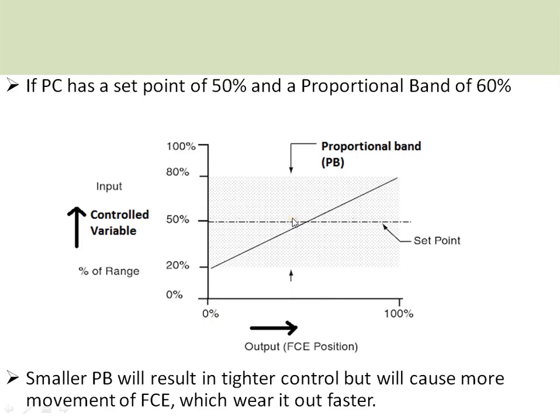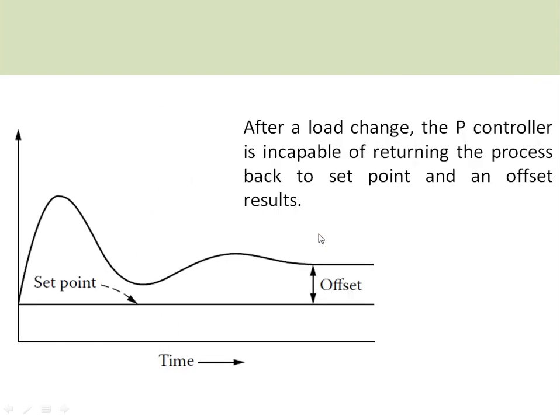A narrower proportional band results in tighter control of the process variable, but introduces more oscillations, which may not be acceptable for certain applications. A wider proportional band results in poorer control but eliminates oscillations. The proportional band is selected depending on your process requirement. One major disadvantage of using only a proportional controller is that the process will not reach the set point — there is an offset, also known as steady-state error. As time tends to infinity, the process variable never reaches the set point.